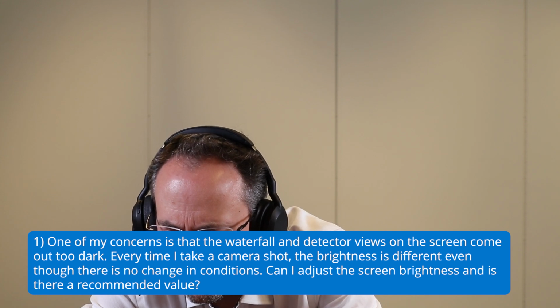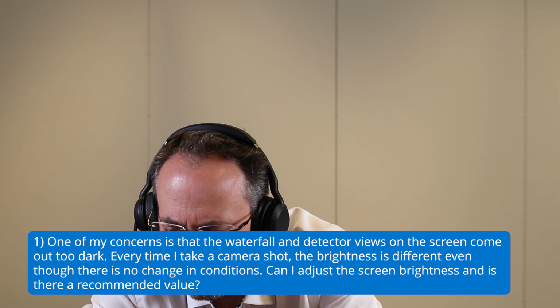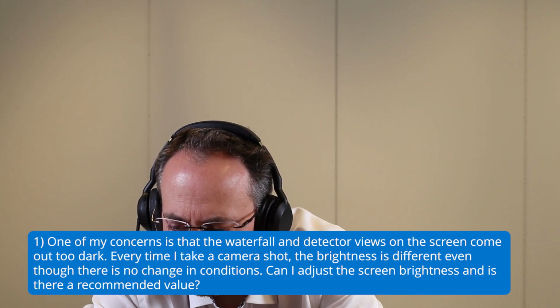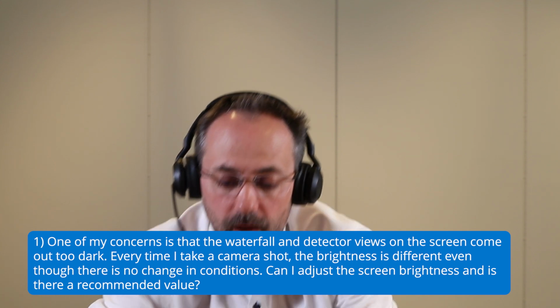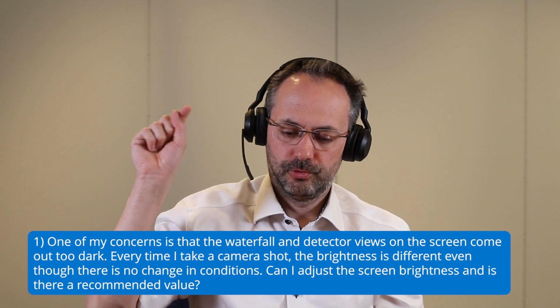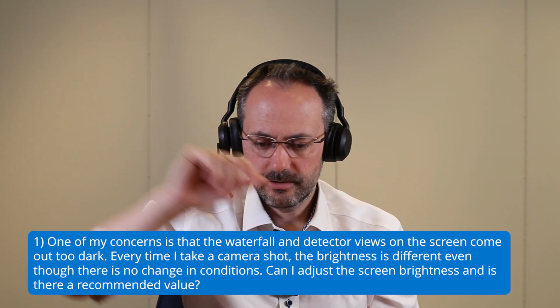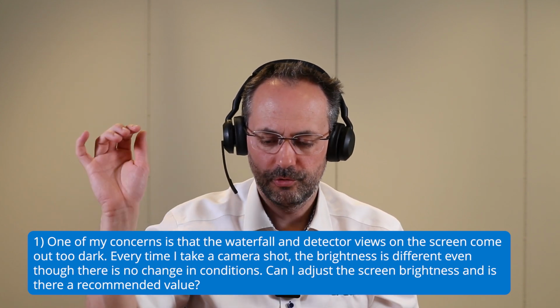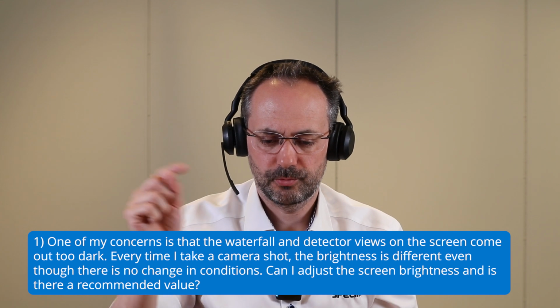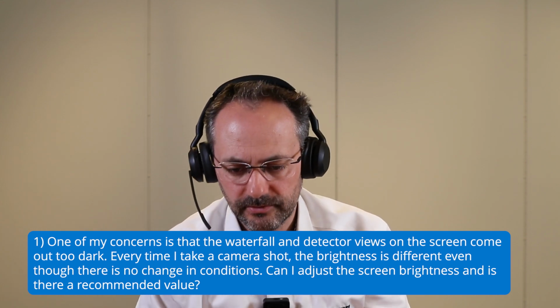One of my concerns is that the waterfall and detector view on the screen come out too dark. Every time I take a camera shot, the brightness is different, even though there is no change in condition. Can I adjust the screen brightness, and is there a recommended value? You go to the right-hand side, where you have the detector view, you do a right-click, and then you can change the brightness and also the contrast.